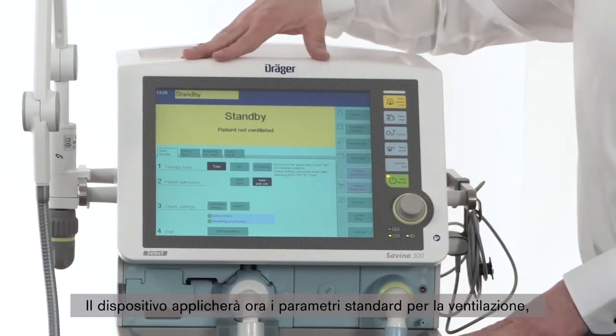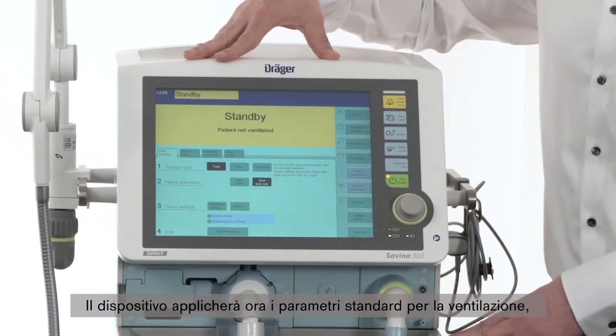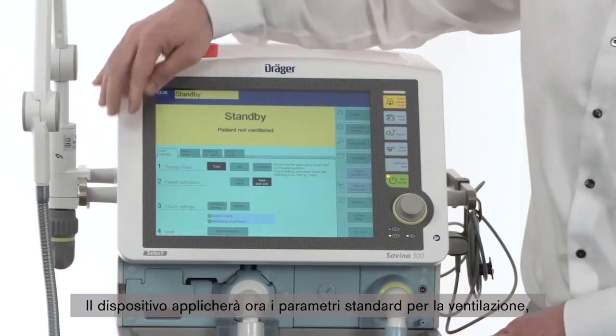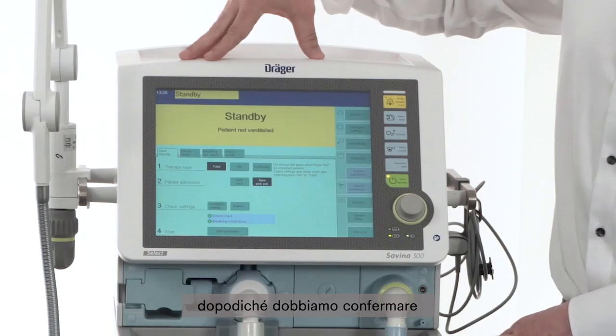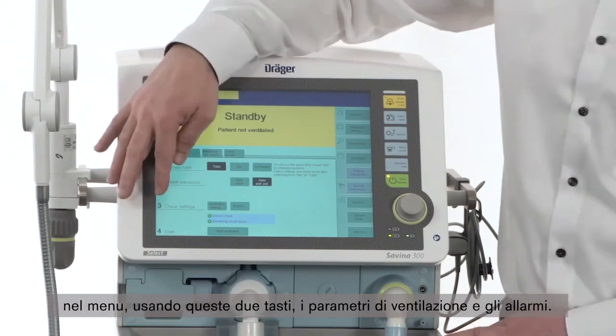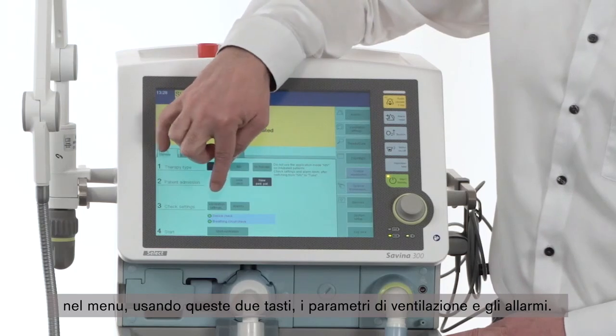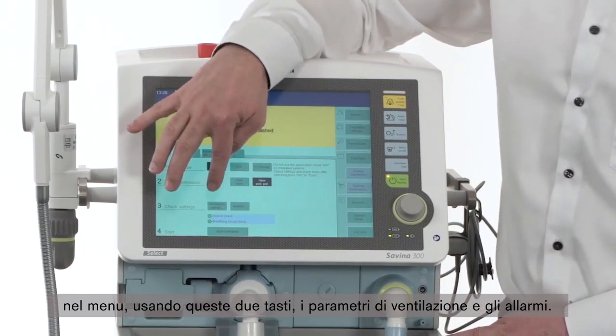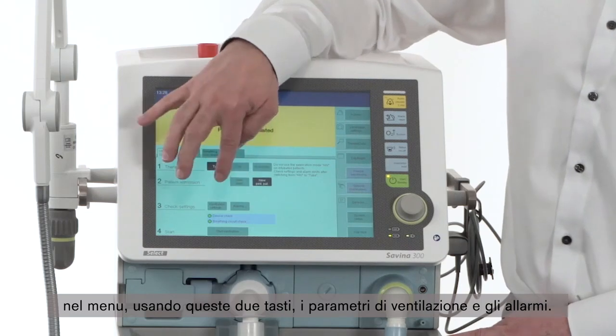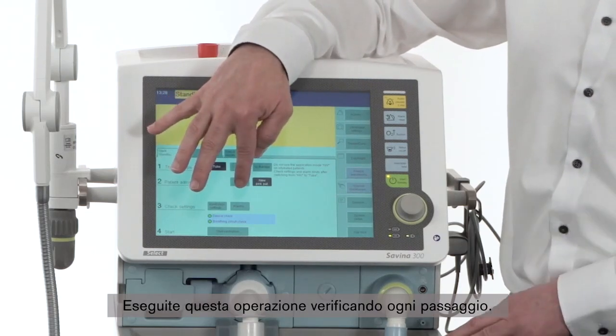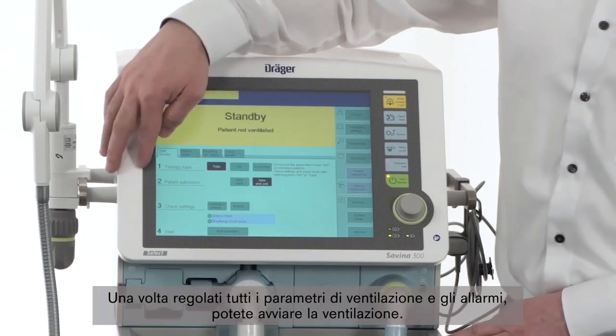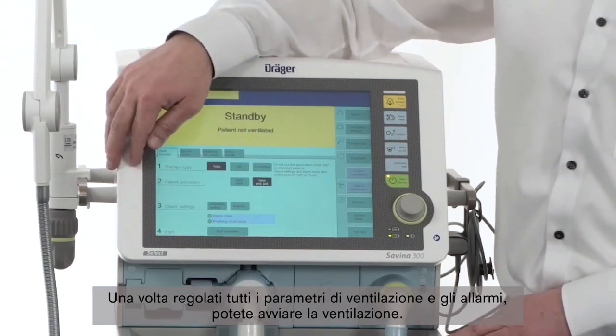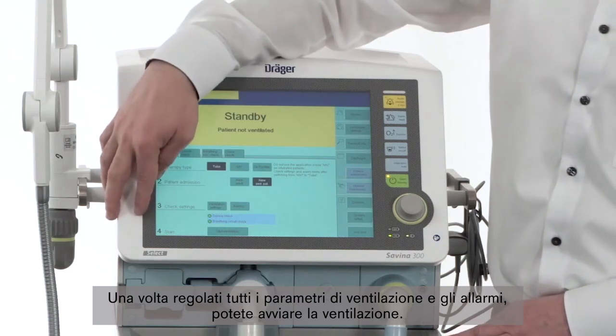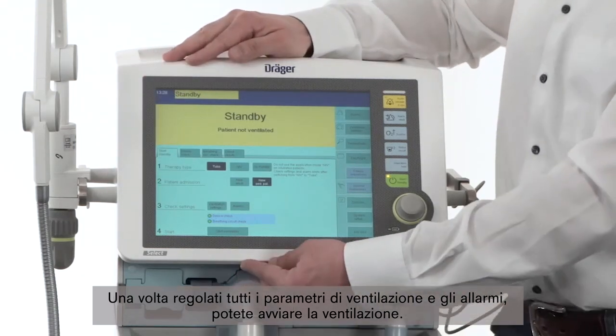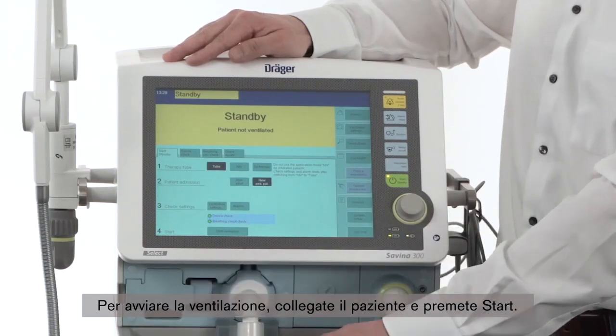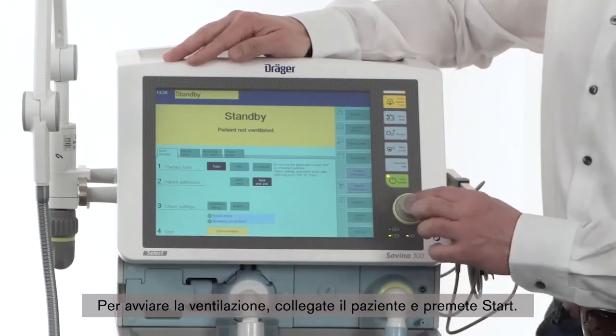The device will now apply standard parameters for ventilation. After you have applied standard parameters for ventilation, please check in the menu by using those two knobs for the ventilation parameters and for the alarms. Please go through this and check it step by step. After all ventilation parameters and alarms have been adjusted, you are ready to start ventilation. Before starting ventilation, connect your patient and start with the ventilation.